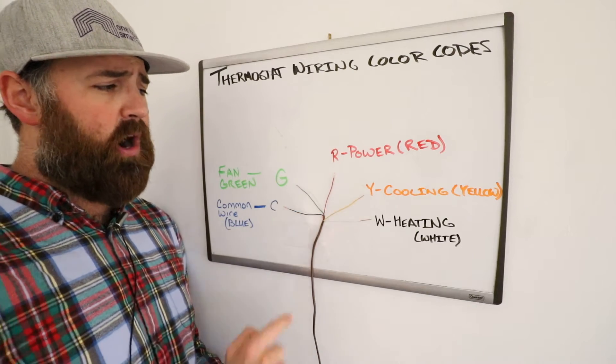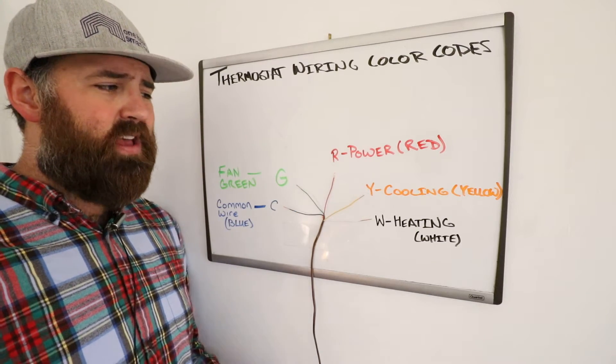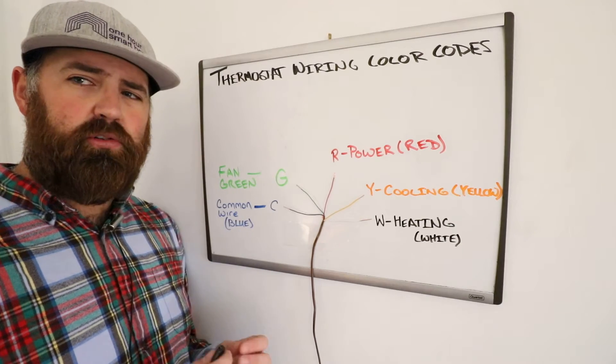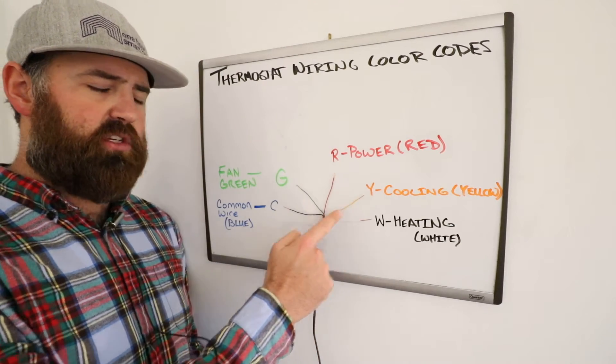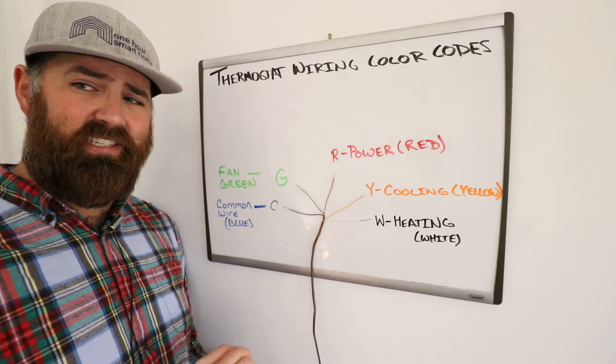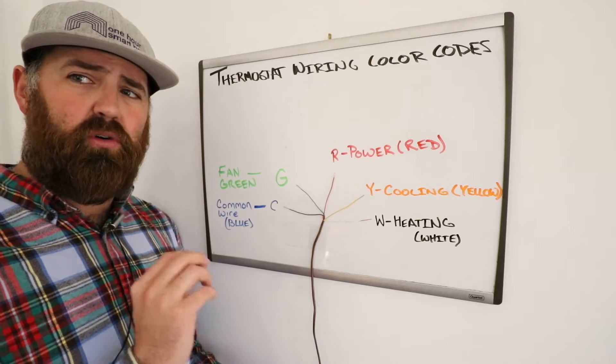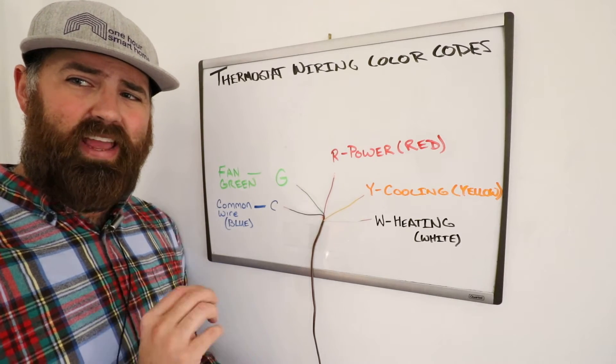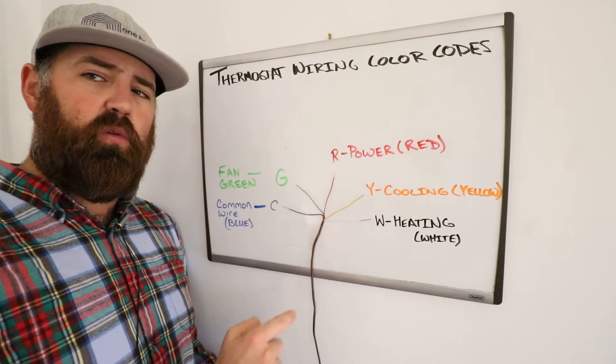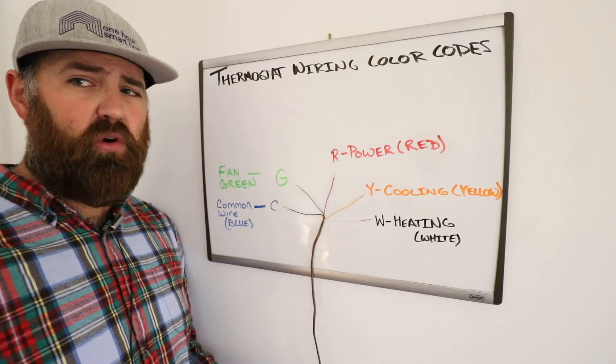So the next wire that we have here is the Y-wire, the yellow wire. That is used for cooling. It controls your air conditioner, and this wire goes all the way back to your HVAC system, connects to a terminal on your HVAC system board, and controls your air conditioner, compressor, and condenser, and when power from the R-wire goes to the Y-wire, it will activate your cooling system.